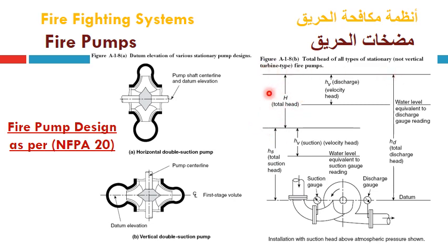This is the total head, which is the difference between the total discharge head minus the total suction head, which is named the total head of the pump after adding both a static term and dynamic term due to velocity head on both sides, suction and discharge lines.